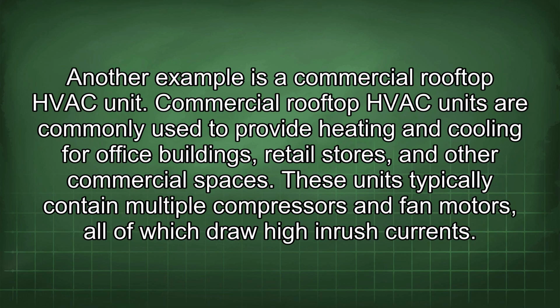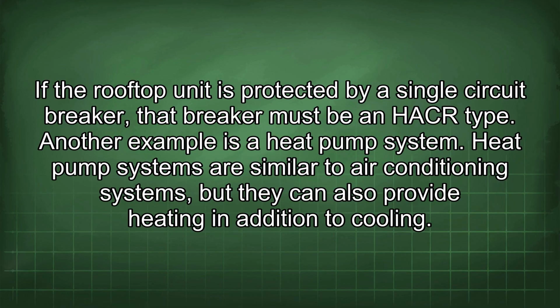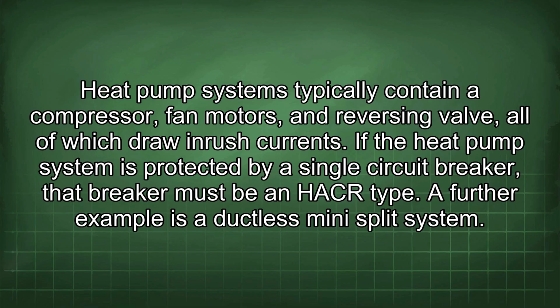Another example is a commercial rooftop HVAC unit. Commercial rooftop HVAC units are commonly used to provide heating and cooling for office buildings, retail stores, and other commercial spaces. These units typically contain multiple compressors and fan motors, all of which draw high inrush currents. If the rooftop unit is protected by a single circuit breaker, that breaker must be an HACR type. Another example is a heat pump system. Heat pump systems are similar to air conditioning systems, but they can also provide heating in addition to cooling. Heat pump systems typically contain a compressor, fan motors, and reversing valve, all of which draw inrush currents. If the heat pump system is protected by a single circuit breaker, that breaker must be an HACR type.